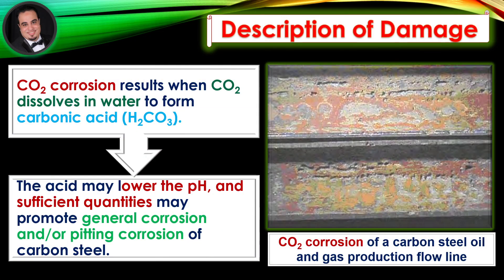Description of damage: Carbon dioxide CO2 corrosion results when CO2 dissolves in water to form carbonic acid. The acid may lower the pH and, in sufficient quantities, may promote general corrosion and/or pitting corrosion of carbon steel, as illustrated in the figure showing an example of CO2 corrosion of a carbon steel oil and gas production flow line.